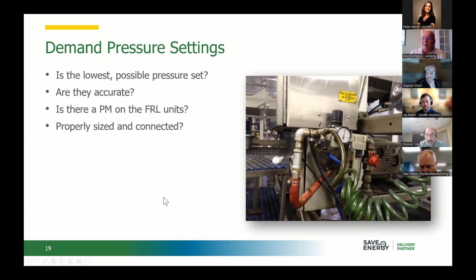So I could have a plugged filter, or too small of an air supply into a regulator that could be causing an issue. You have to look at the point of use pressure regulators. If you've got a large flow controller that can take the entire system down at 90, don't just stop there, go to all your pieces of equipment. If your regulator can be dropped from 90 to even 85 or lower, those are the opportunities for energy savings. You do the whole plant as low as you can, and at point of use you drop it even further if you can. So you kind of have to have your arms around the whole thing to do this properly.